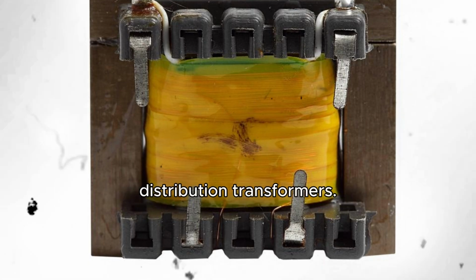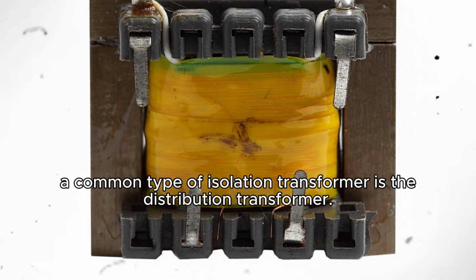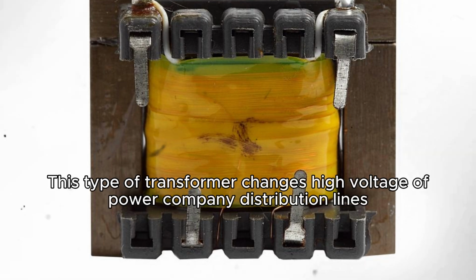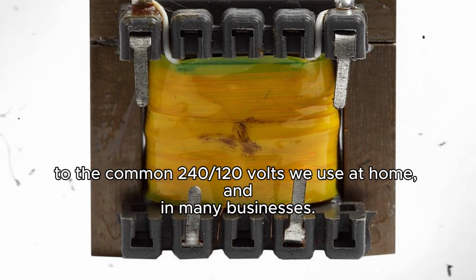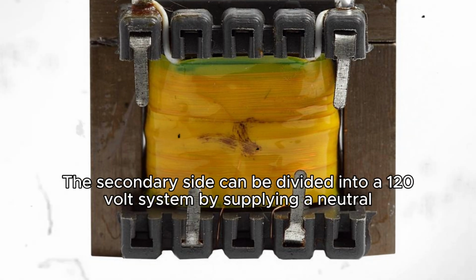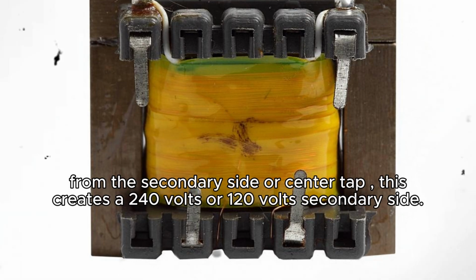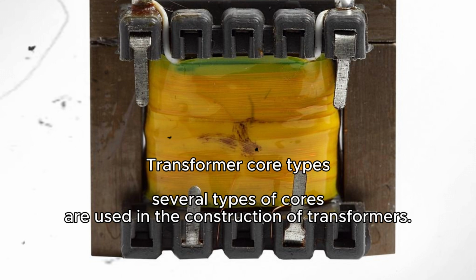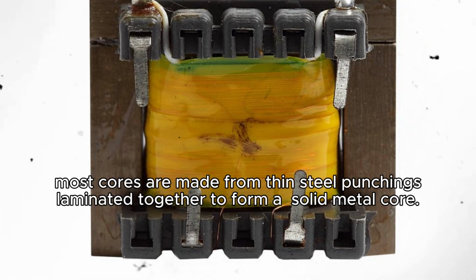Distribution transformers. A common type of isolation transformer is the distribution transformer. This type of transformer changes the high voltage of power company distribution lines to the common 240/120 volts we use at home and in many businesses. The secondary side can be divided into a 120-volt system by supplying a neutral from the secondary side center tap. This creates a 240 volt or 120 volt secondary side. Transformer core type. Several types of cores are used in the construction of transformers. Most cores are made from thin steel punchings laminated together to form a solid metal core.